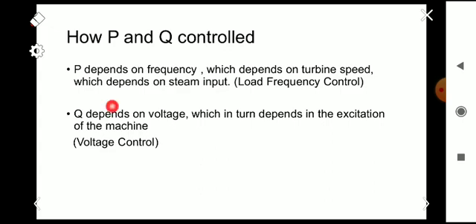Likewise, for controlling Q — the reactive power — as we know Q depends on voltage, which in turn depends on the excitation of the machine, that is the excitation voltage of the generator. So for controlling Q we have to control the voltage, and the voltage is mainly controlled by controlling the excitation of the machine.